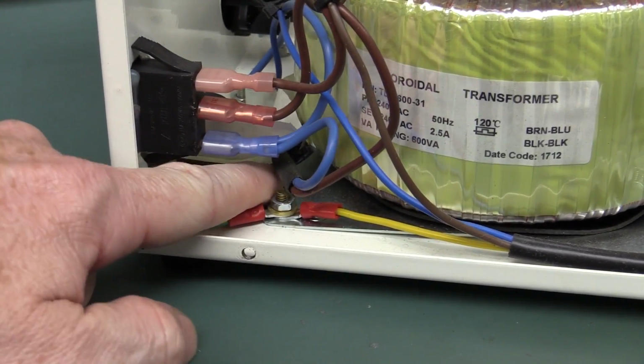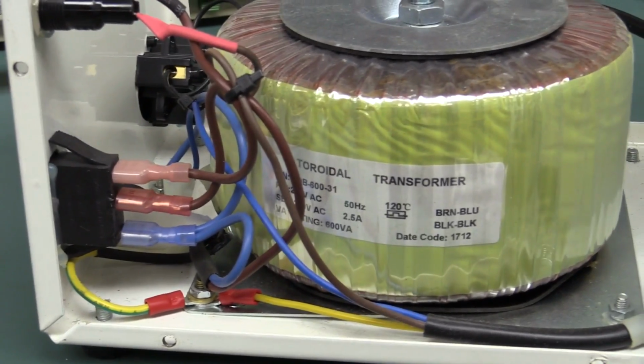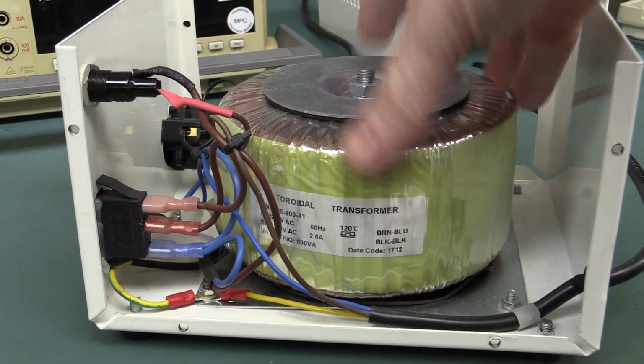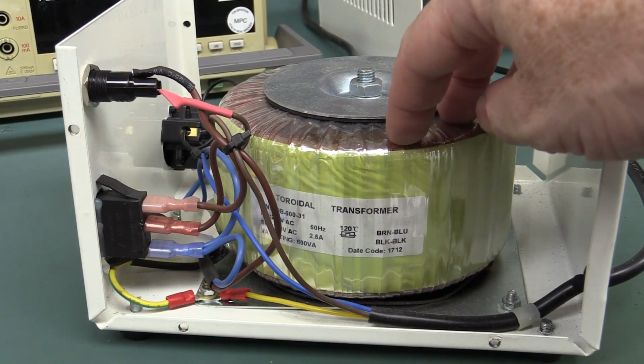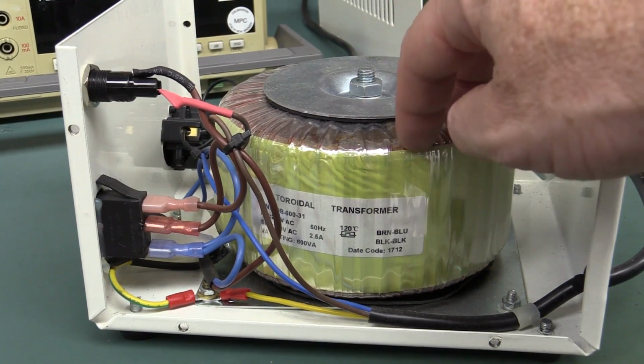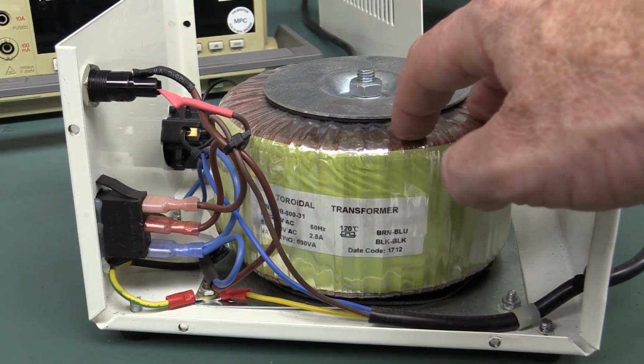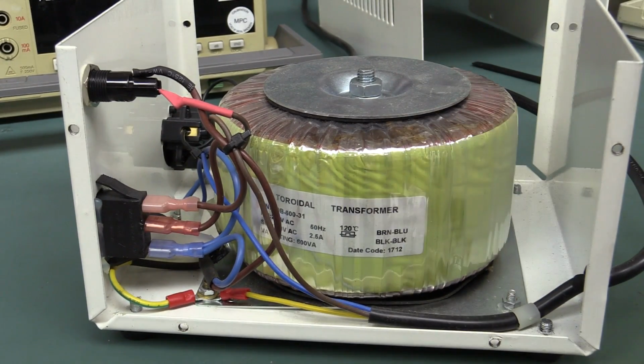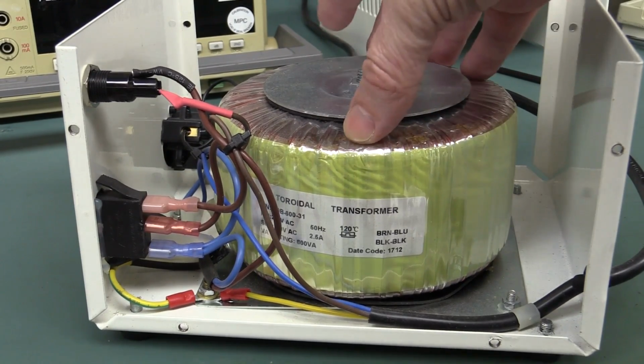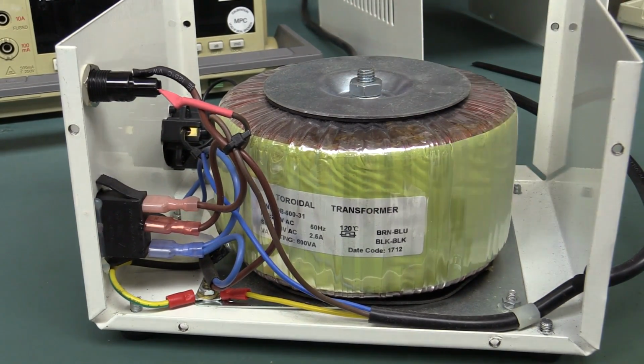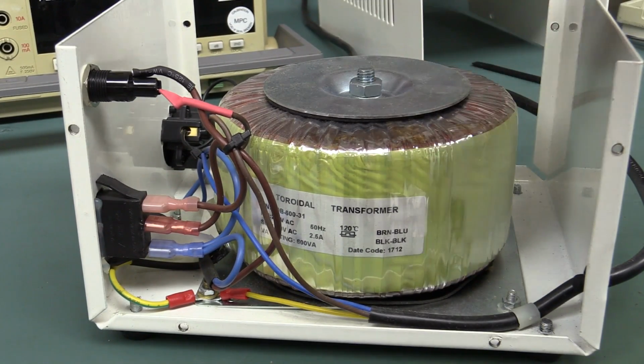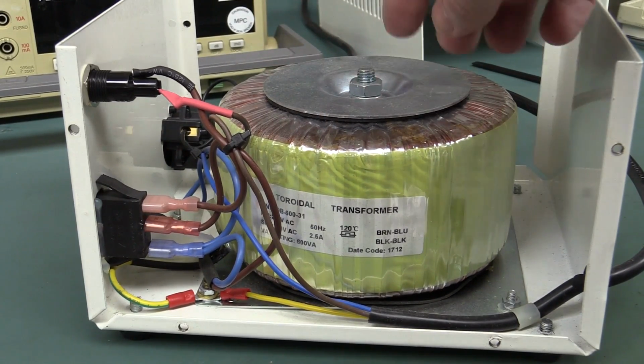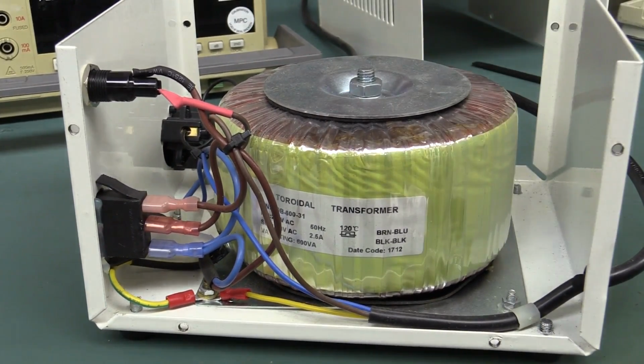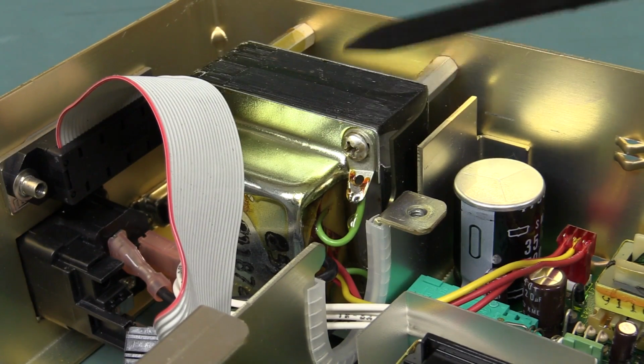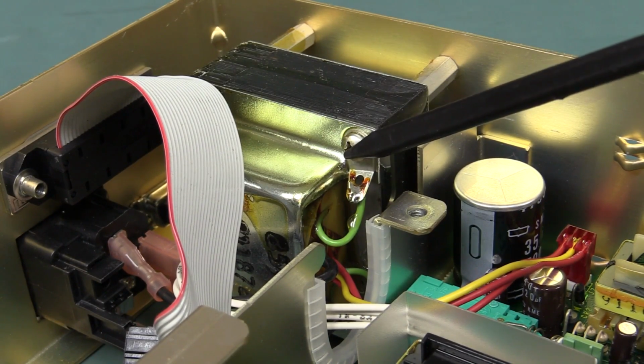Anyway, it's going inside the transformer because they've got an electrostatic shield inside, between the primary and the secondary. That basically cuts the capacitance completely down to zero, so there's no coupling between the primary and secondary. Common mode noise can't get through from the primary side over to the secondary. That internal electrostatic shield is going to be closely coupled to the primary side. So Fluke are doing exactly the same thing inside this transformer to get that common mode noise down.